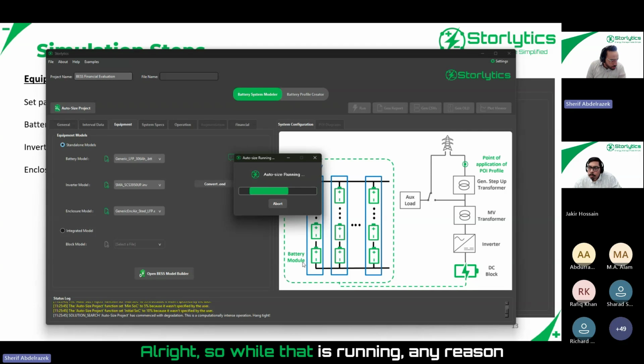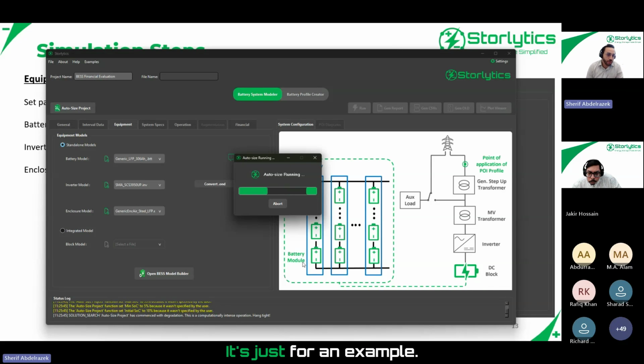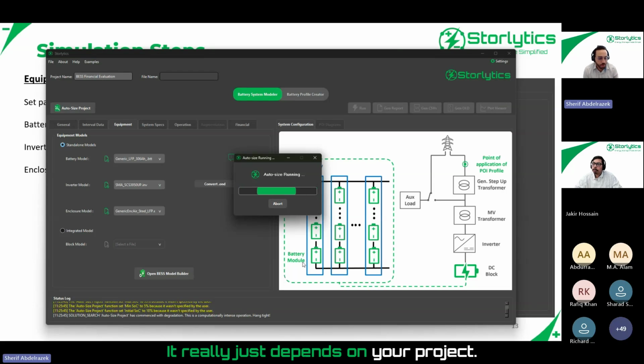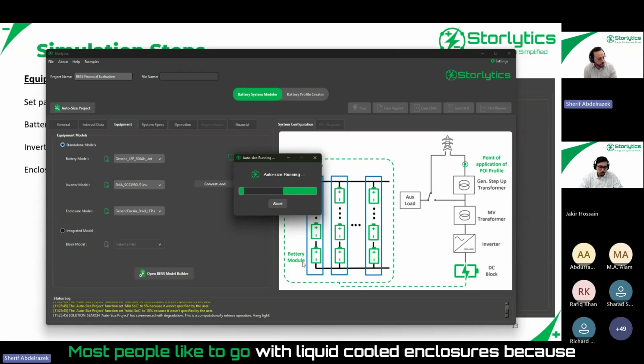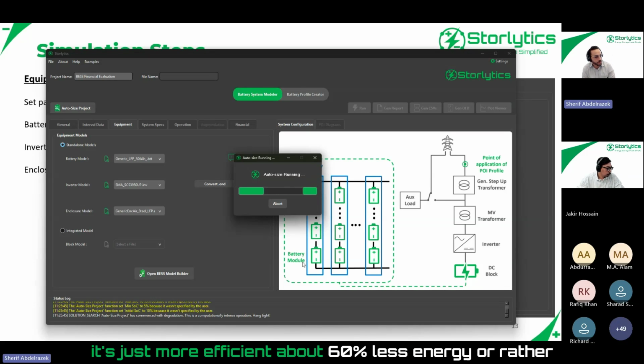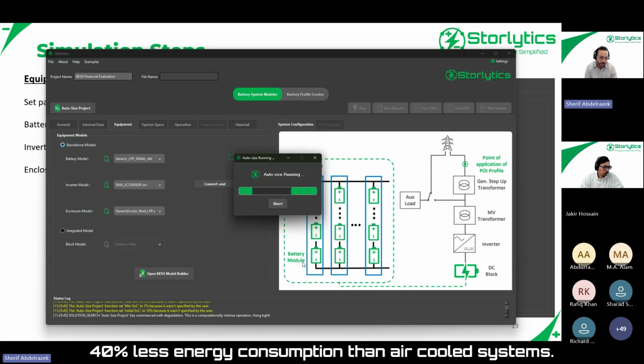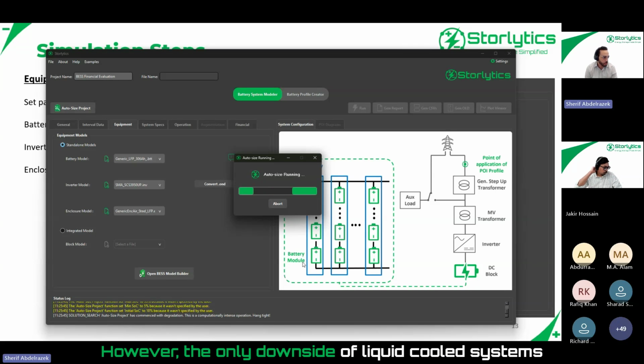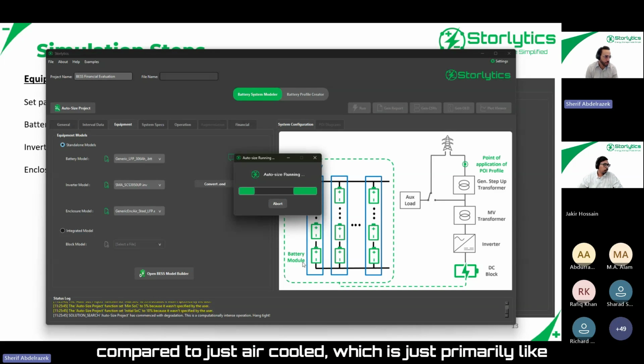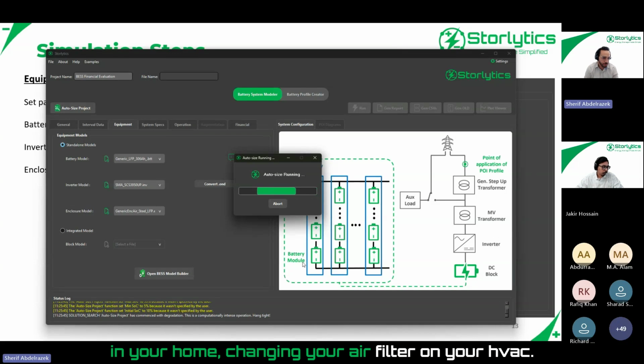All right. So while that is running, any reason we did not choose a liquid-cooled enclosure? No, there's no reason. It's just for an example. It really just depends on your project. Most people like to go with liquid-cooled enclosures because it's just more efficient, about 40% less energy consumption than air-cooled systems. However, the only downside of liquid-cooled systems is the extra maintenance that is required for them compared to just air-cooled, which is primarily like in your home, changing your air filter on your HVAC.